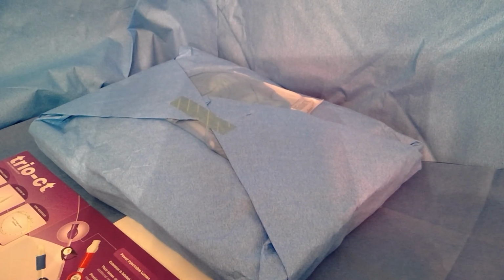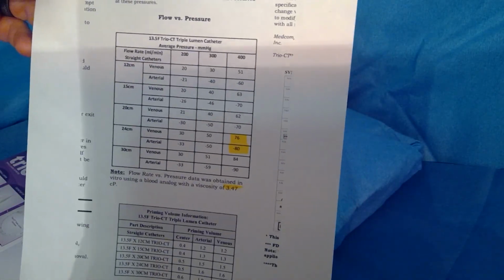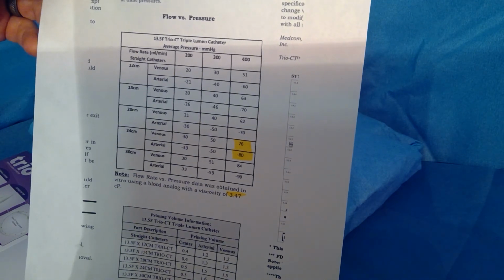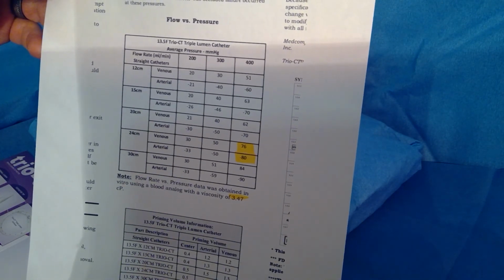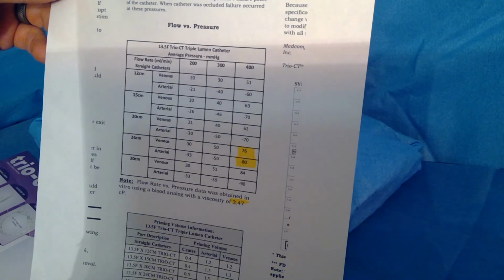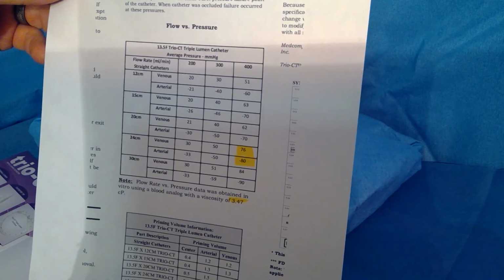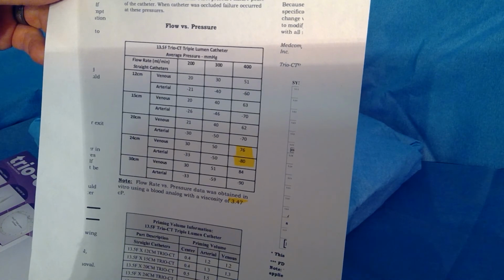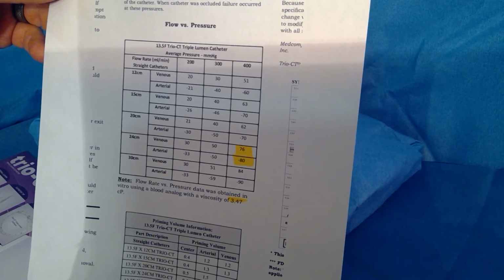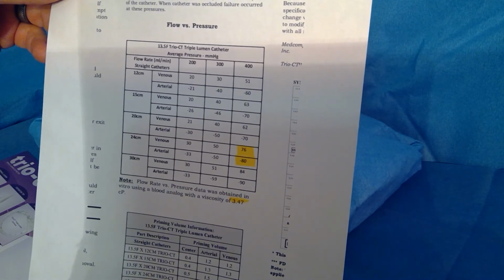And it's actually interesting if you look at the actual IFUs. Those numbers that I just went over are from head-to-head studies our engineers do. But if you actually look at the IFUs, it's even more interesting. Here's our IFU insert that's in every package, and it shows you that at 400 flows, a 24 centimeter Trio CT catheter, they're all 13.5 French, 24 centimeter. Venous is 76, average pressure is 76, arterial is -80, and that is at 400 flows.